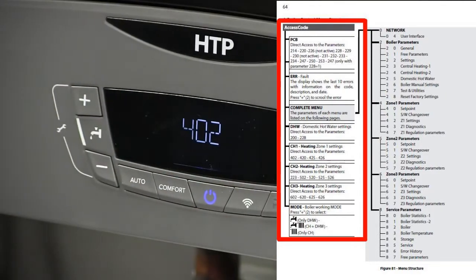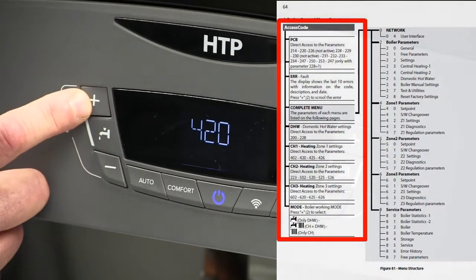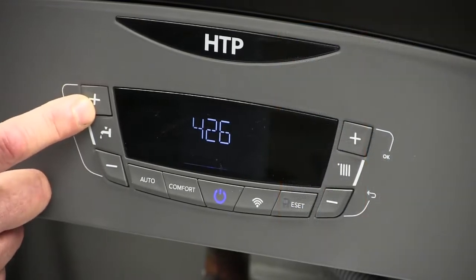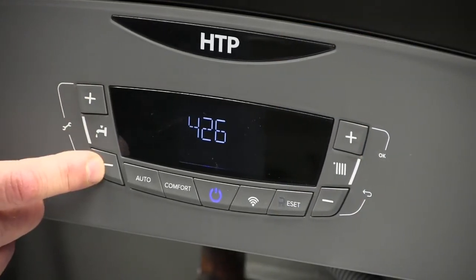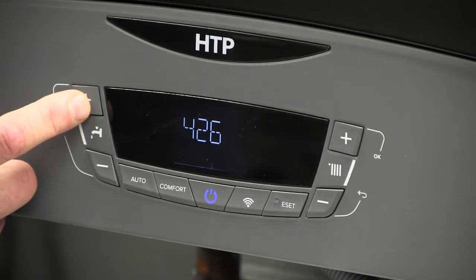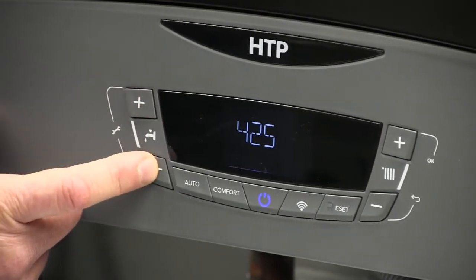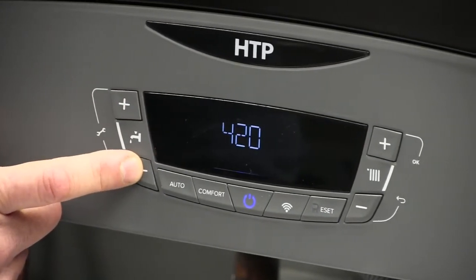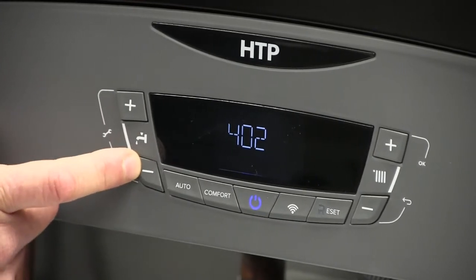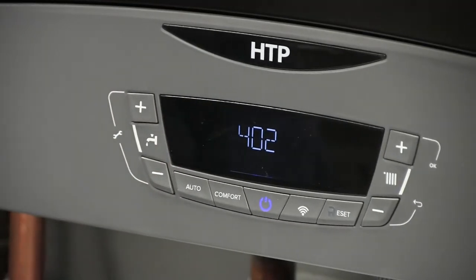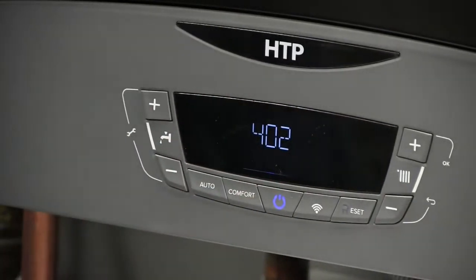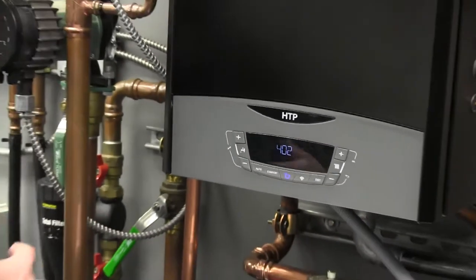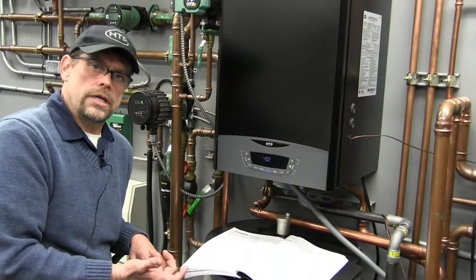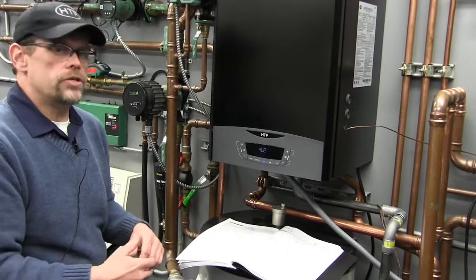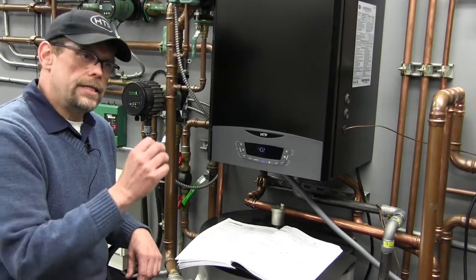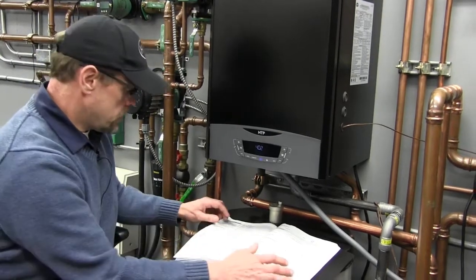We hit OK. Remember, there will be 4: the 402, the 420, 425, and 426. This would be the minimum temperature for outdoor reset, that would be the maximum temperature, whether we're in a high temp or low temp system, and last but not least, the set point temperature. But nowhere in those 4 settings does it allow us to change the warm weather shutdown temperature. So we're going to have to enter the full menu, get to that item, and make the adjustment.